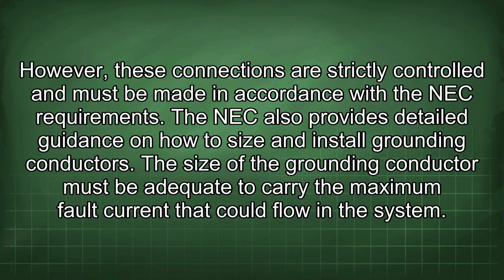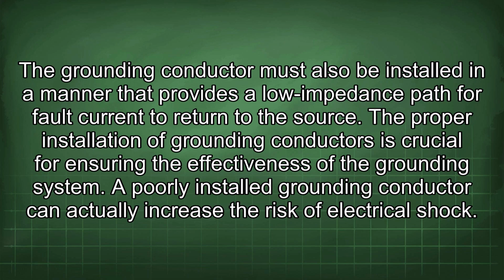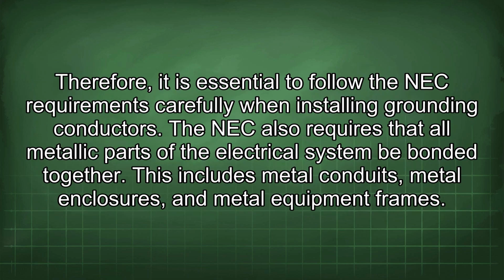The NEC also provides detailed guidance on how to size and install grounding conductors. The size of the grounding conductor must be adequate to carry the maximum fault current that could flow in the system. The grounding conductor must also be installed in a manner that provides a low impedance path for fault current to return to the source. The proper installation of grounding conductors is crucial for ensuring the effectiveness of the grounding system. A poorly installed grounding conductor can actually increase the risk of electrical shock. Therefore, it is essential to follow the NEC requirements carefully when installing grounding conductors.